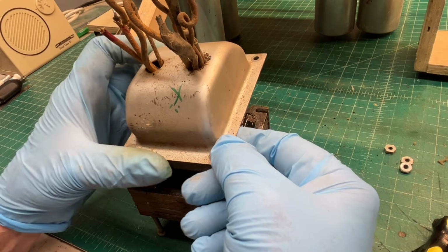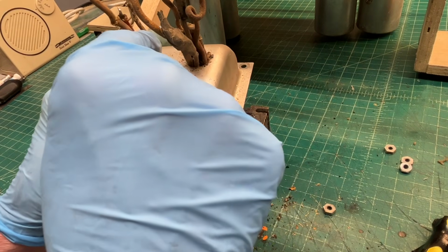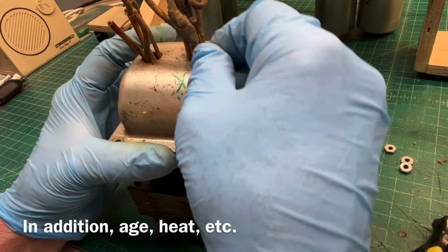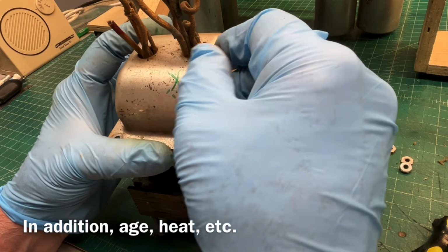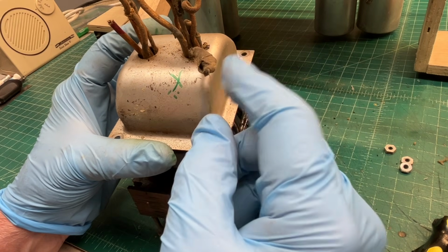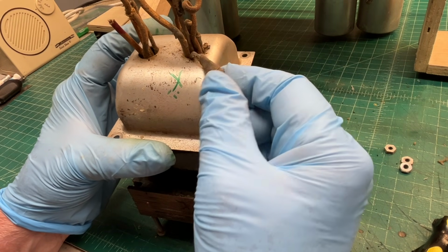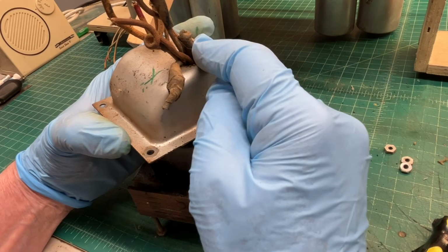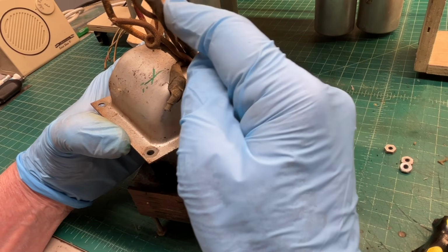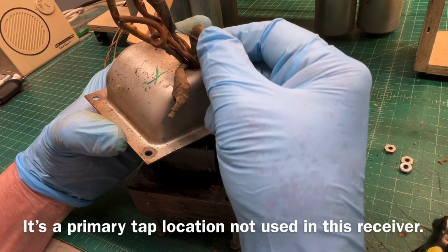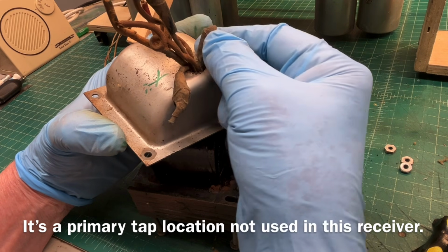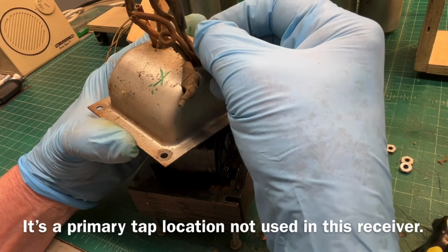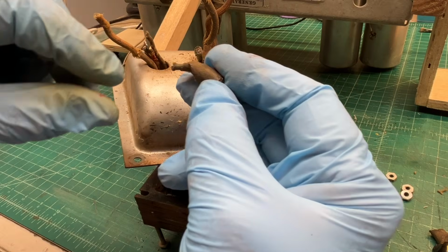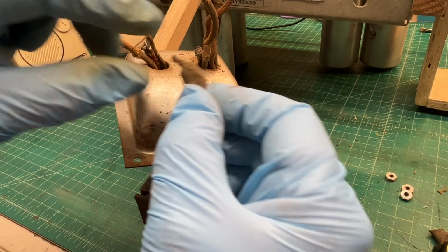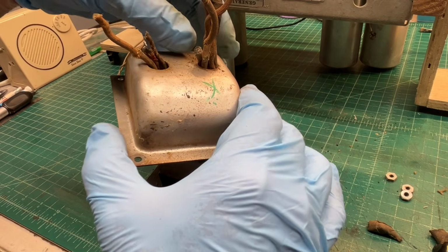You can see why that occurs - the leads are bent when they come out of the transformer, and you can see how tight they are as well. This lead was just taped off and not used on this particular transformer. Let me see if I can push that through - I just had to snip it where the primary was spliced so I can get that through.